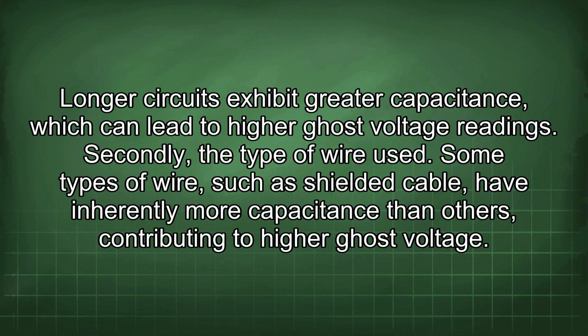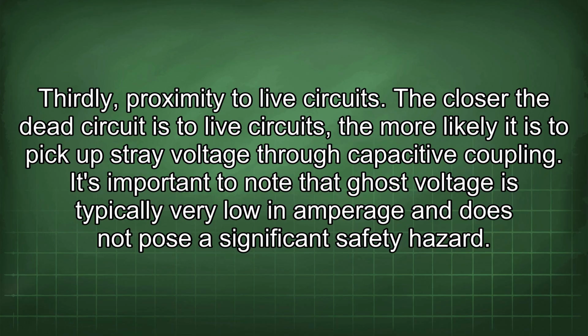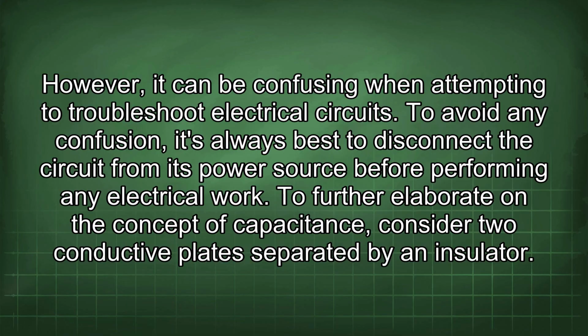Secondly, the type of wire used. Some types of wire, such as shielded cable, have inherently more capacitance than others, contributing to higher ghost voltage. Thirdly, proximity to live circuits. The closer the dead circuit is to live circuits, the more likely it is to pick up stray voltage through capacitive coupling. It's important to note that ghost voltage is typically very low in amperage and does not pose a significant safety hazard. However, it can be confusing when attempting to troubleshoot electrical circuits. To avoid any confusion, it's always best to disconnect the circuit from its power source before performing any electrical work.